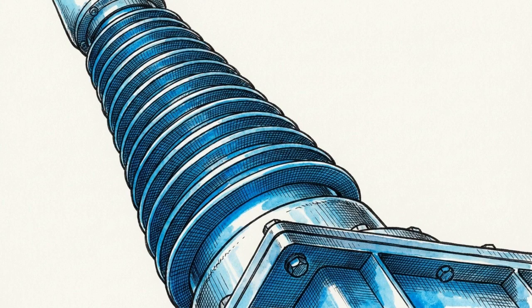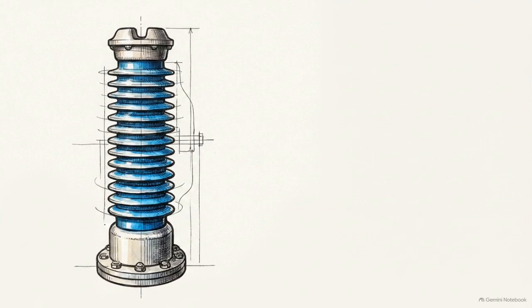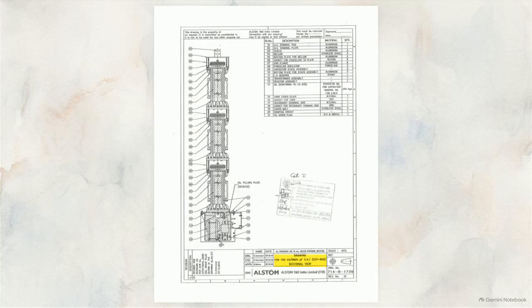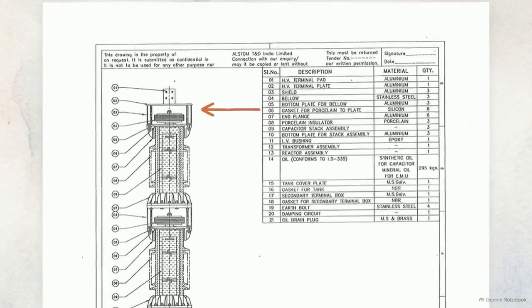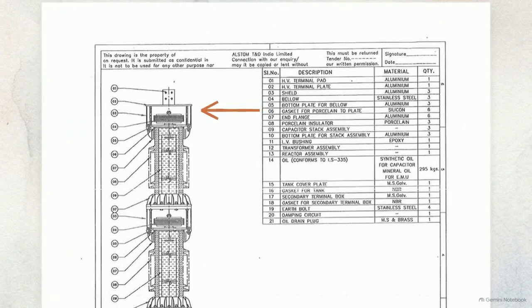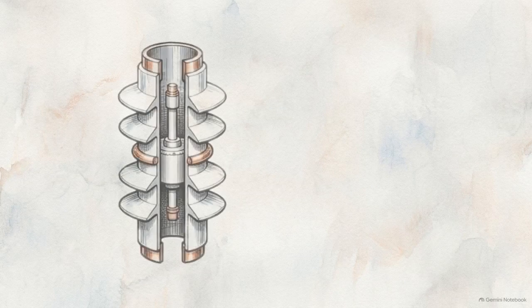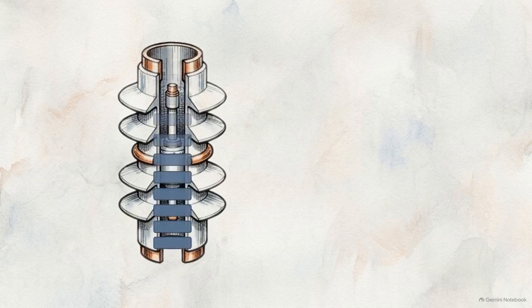The first stage happens entirely within the tall, towering section that connects directly to the power line. This upper section is known as the capacitive voltage divider. Looking at the engineering schematic for a 765 kV unit, we see how it reduces the incoming voltage. The column is housed inside a weatherproof outer shell made of heavy-duty porcelain. The actual active components doing the work are stacked tightly inside. These are individual capacitor units wired together in one continuous vertical series connection.